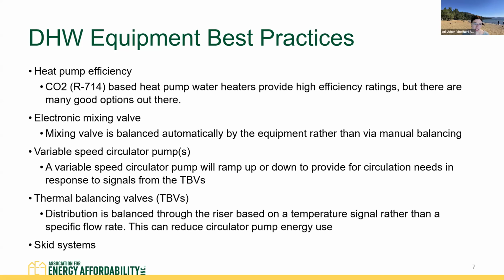And then in terms of circulation, we do need to run those circulation pumps, which does use energy, but we can make sure that it's a very energy efficient recirculation line. The way to do that is with a variable speed circulator pump. This will allow it to ramp up and down to provide only the amount of water that needs to be circulated. And combined with that, we'll use thermal balancing valves, which allow distribution to be balanced through each riser based on a temperature signal rather than a specific flow rate. And overall, this will reduce the circulator pump energy use.